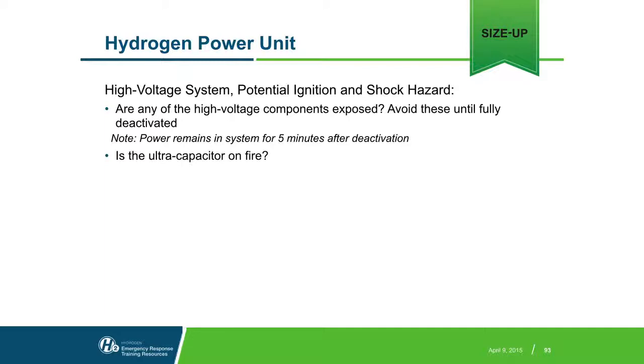So there is the high voltage there. However, if we have powered it down via the e-stop or a regular shutdown, that high voltage is interrupted and the residual power in the lines is dissipated. The ultracapacitors will have charge initially on shutdown and will dissipate over time, so over a matter of hours, because there's a lot of charge.